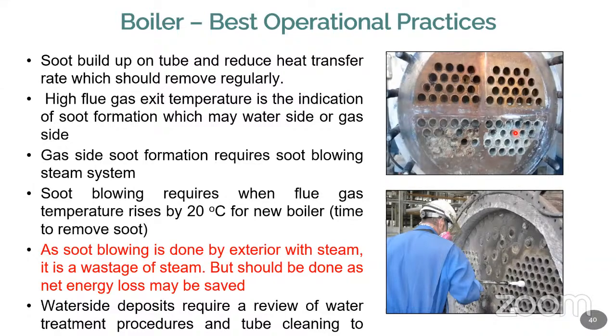So the operating practices for the boiler are a very huge list. Okay. So at regular intervals, you have to go for a blow down. At regular intervals, you have to remove the soot formation inside the tubes, and at regular intervals, you can go for some chemical treatment for your boilers. And similarly, not only the system, the flue gas chimney also you have to clean, because if the chimney is not cleaned, automatically the carbons are deposited in the flue gas chamber, so that will not allow the flue gas to go outside the chimney. So that will again block. The chimney will heat up. So many things are there.